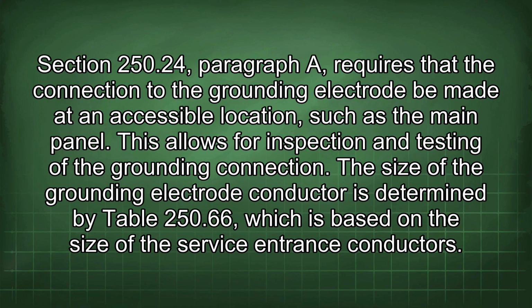Section 250.24, paragraph A requires that the connection to the grounding electrode be made at an accessible location, such as the main panel. This allows for inspection and testing of the grounding connection. The size of the grounding electrode conductor is determined by Table 250.66, which is based on the size of the service entrance conductors.